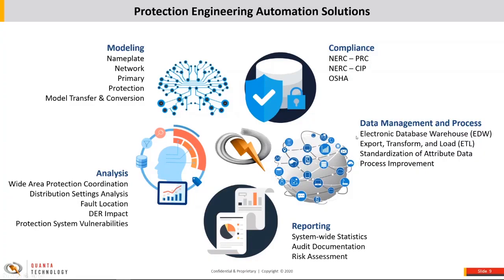Data management and processes: providing data for operations in a live system, looking at how you can integrate relay settings for integrated capacity assessment or adaptive protection — things that operations need to know in a live basis. Reporting: protection engineers get quite overloaded with reporting requirements from other departments, such as CT ratios for calculating FAC-008 for planners, or providing minimum trip or specific relay functionalities for operations.